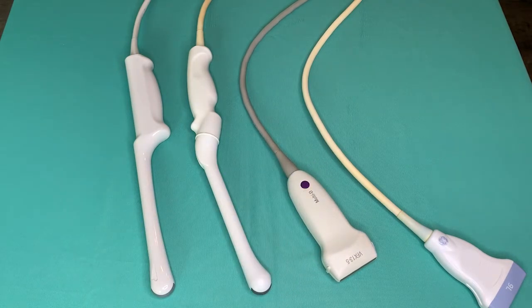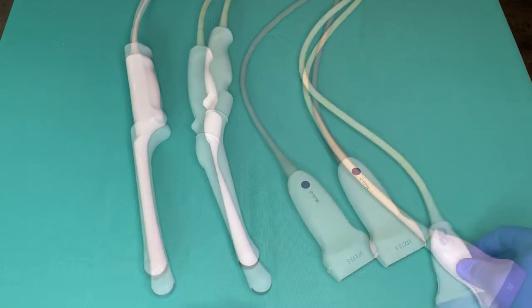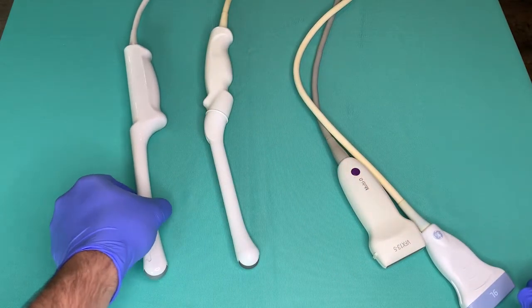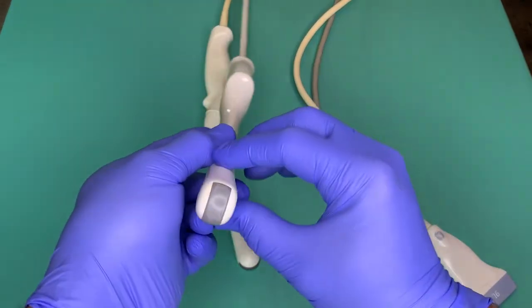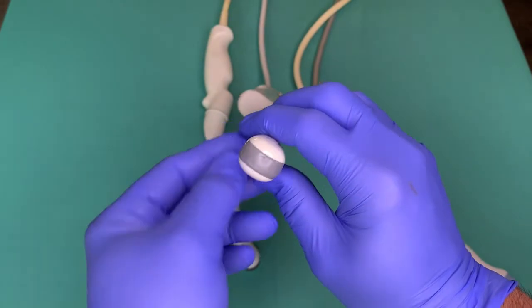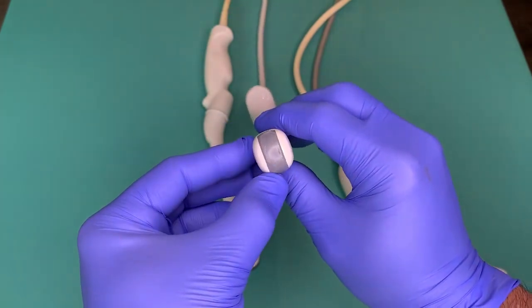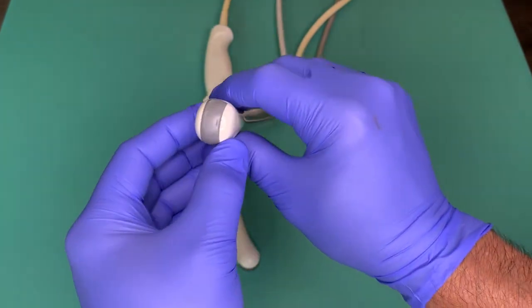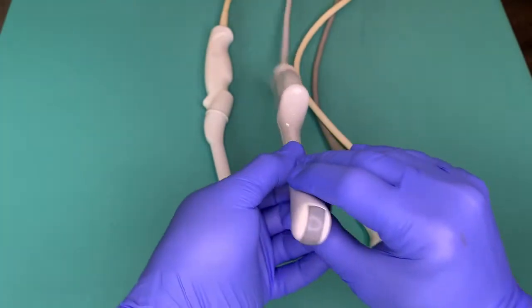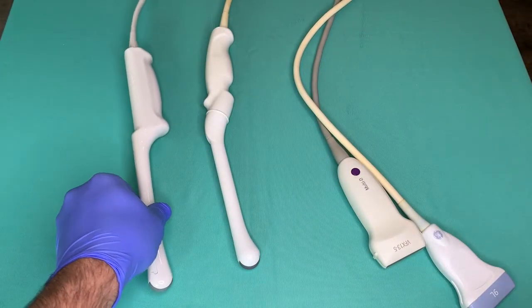The lens on some Philips probes is coated with a clear coating that will peel away over time and may even appear fractured. It's acceptable and can be considered part of normal wear and tear. The peeling or lack of a clear coat does not affect performance and poses no safety risk.